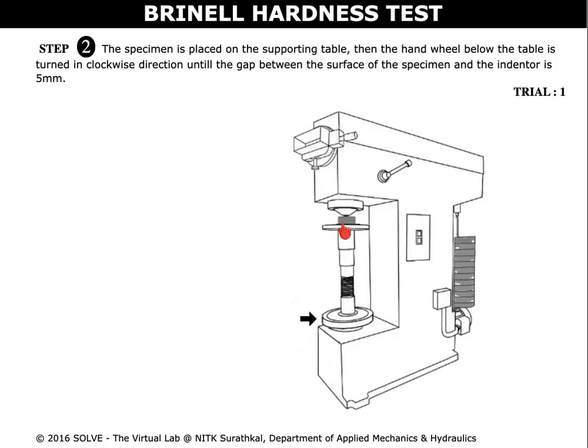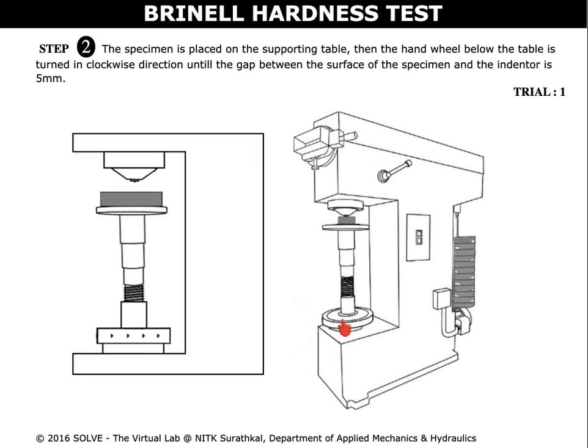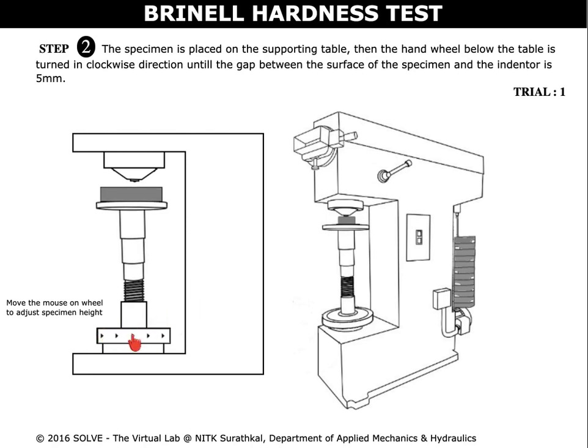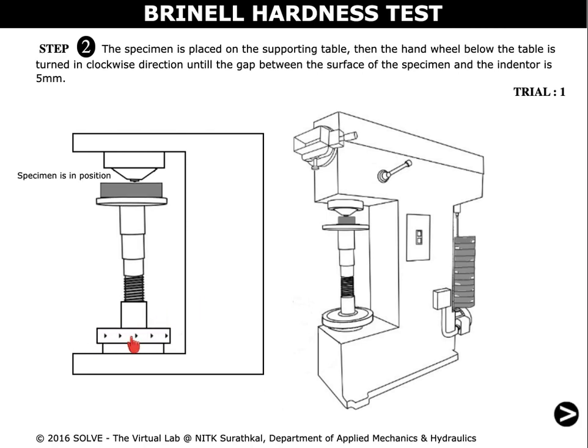The specimen is placed in the supporting table. Now click on the hand wheel and move the mouse pointer in the clockwise direction to position the specimen. There should be a 5 mm gap between the surface of the specimen and the indentor.